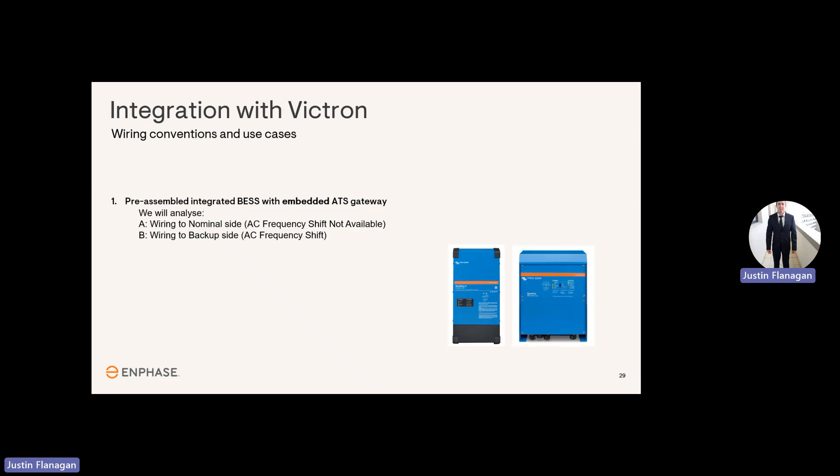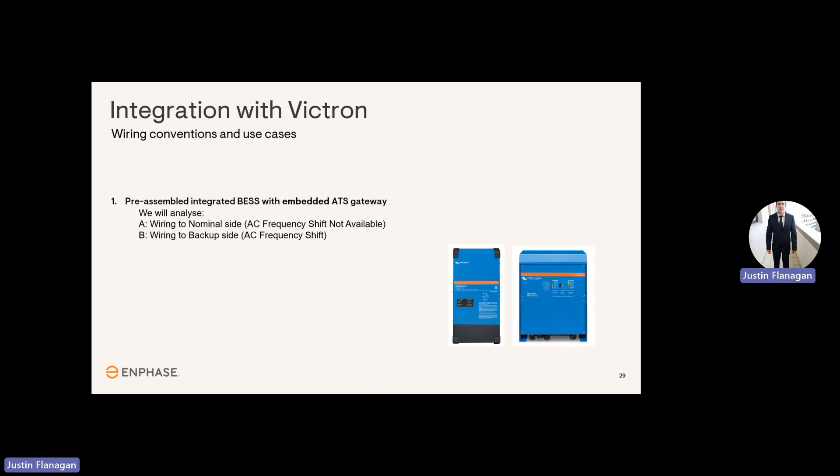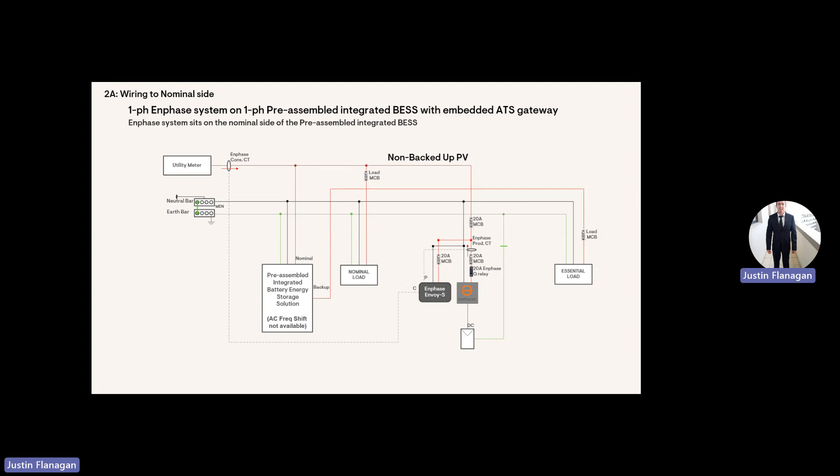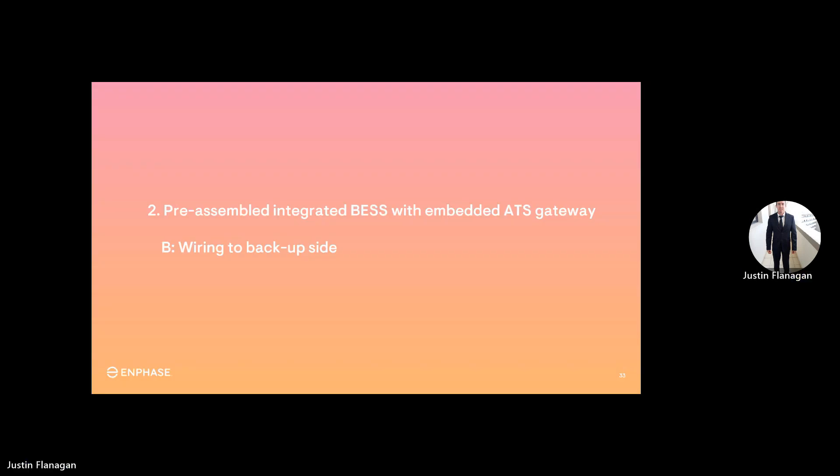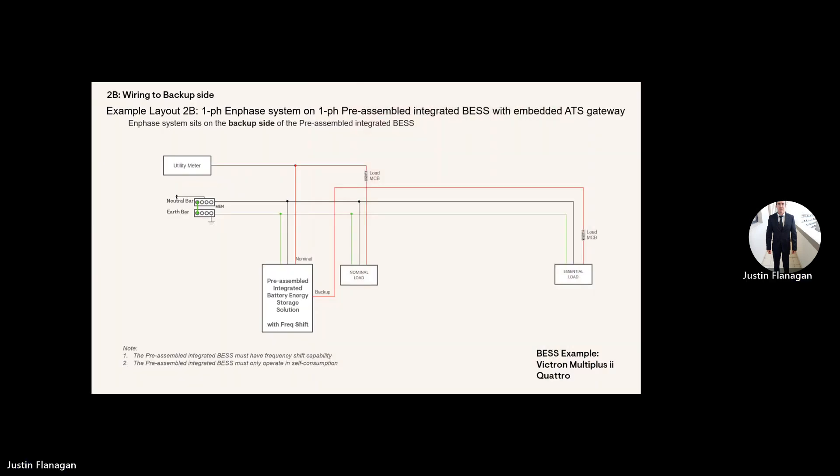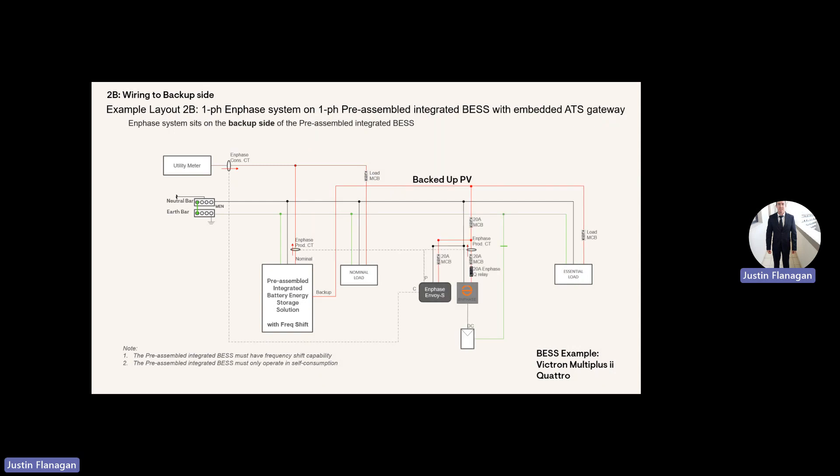Integration. We'll have a look at some SLDs. The first SLD will show if the third party inverter does not have frequency shift available, and in Victron's case, it has AC frequency shift on the second SLD. This is the first SLD example with no frequency shift available. Your PV system will be connected on your normal side, which means in the event of a grid failure, your PV will switch off, but your battery will still supply the essential loads. With Victron, our PV system will be connected on the backup side or the AC output of the Victron system. In the event of a grid outage, the PV will still stay on, supply power to your essential loads, and keep charging the battery if it's not fully charged.